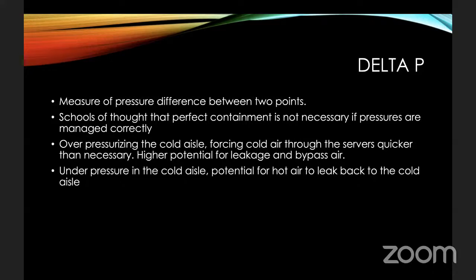So you don't want the pressure in your cold aisle to be too high because it will find its way through those gaps. But you also don't want it to be too low because you don't want hot air coming back into the cold aisle. But the only way that you can actually make sure this is working is through monitoring. You cannot fix or measure if you're not monitoring it. So you need the sensors in place in order to tell you what these pressures are, the same as you need the sensors in place in order to tell you what the temperatures are.